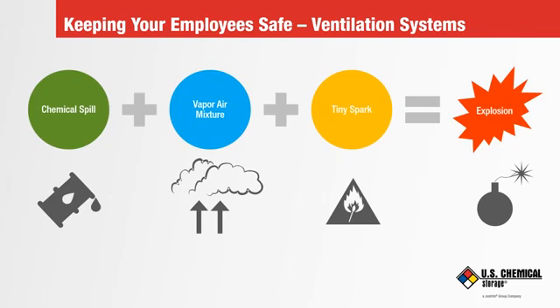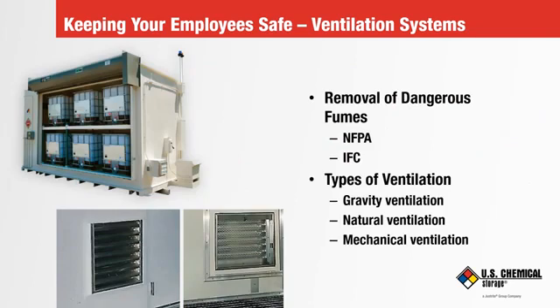NFPA 30 Flammable and Combustible Liquids Code, paragraph A-4-6 says simply, quote, "Ventilation requirements include mechanical ventilation where dispensing operations are expected," unquote. We'll talk more about the different types of ventilation systems on the very next slide.